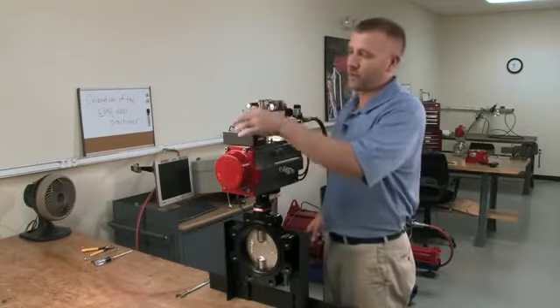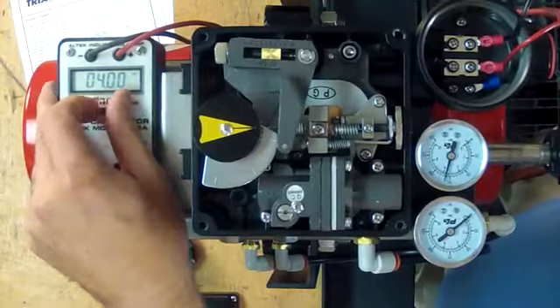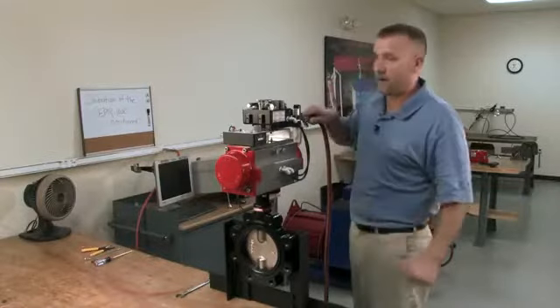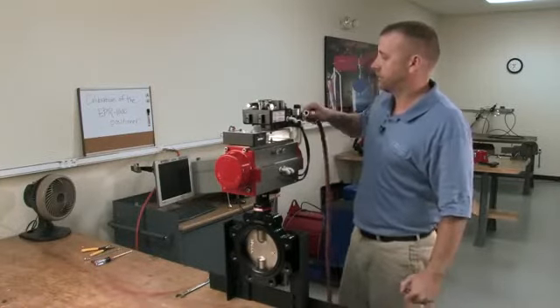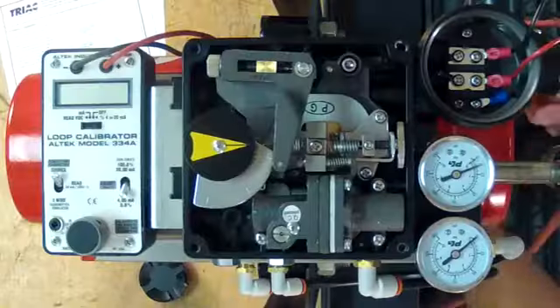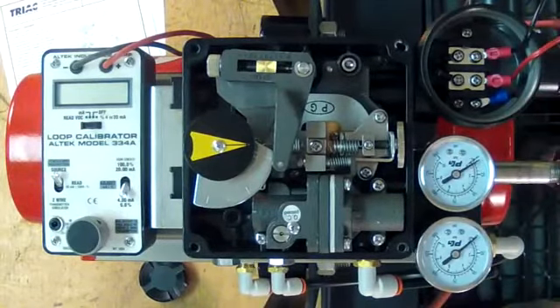So now we're going to just turn the power off to the calibrator, unhook our air line, and that is your basic calibration of your EPR 1000 positioner.